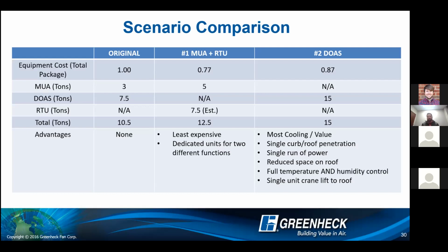The traditional design is going to be the least expensive, right? So that makeup air and the rooftop unit is going to be your least expensive, but we lose humidification. And then finally, kind of that midpoint is your DOAS unit, right? So it should be pretty straightforward. Or I don't want to make that assumption because you can't chime in, but with this DOAS unit, you're going to have your most cooling value. You're going to have a single roof penetration, so that could be very important depending on your roof space. You may just not have the roof space for a traditional makeup air and a rooftop unit.